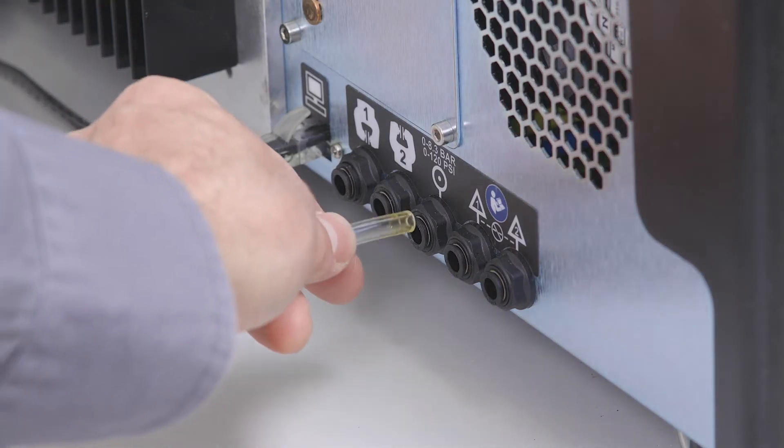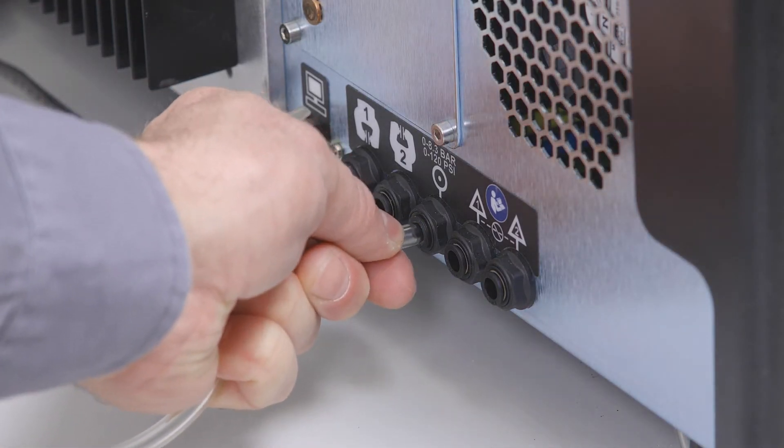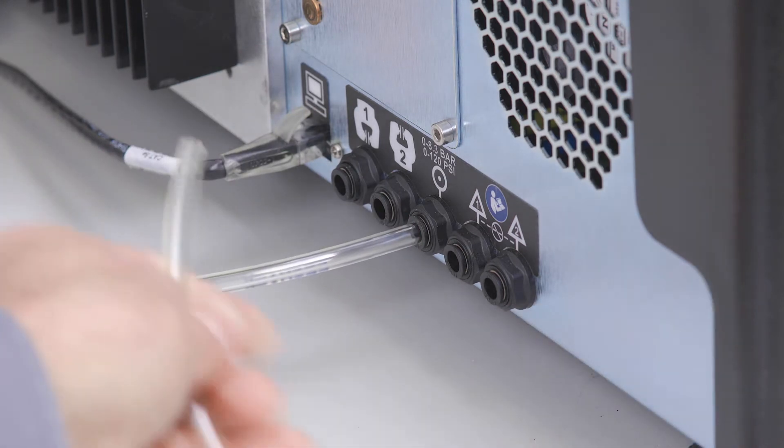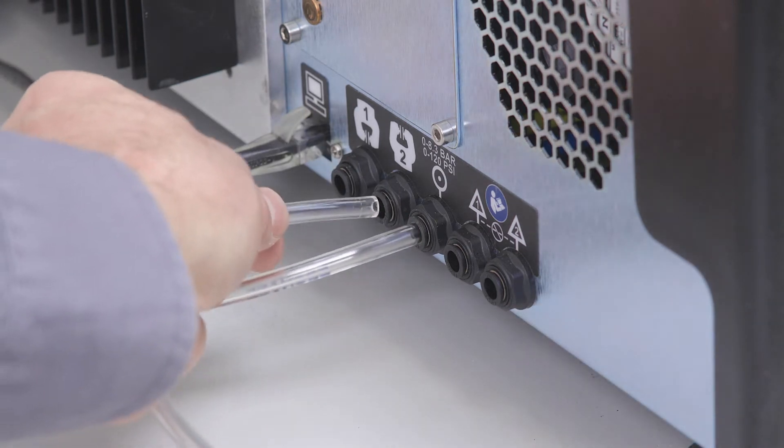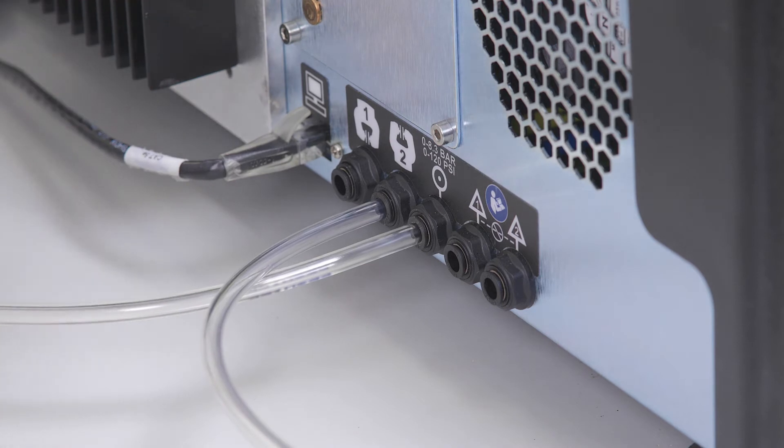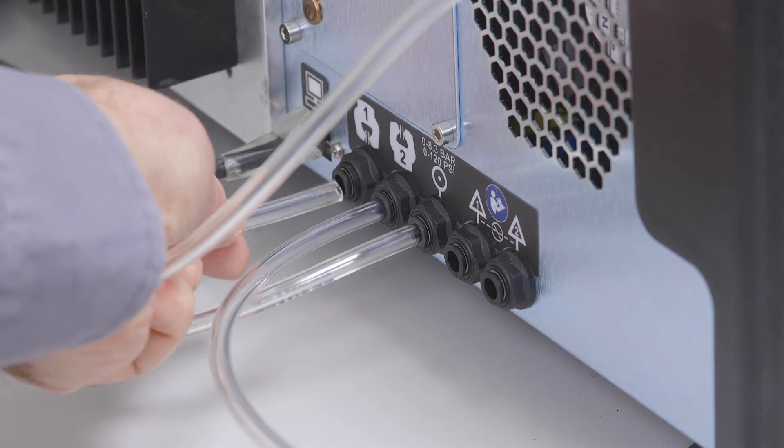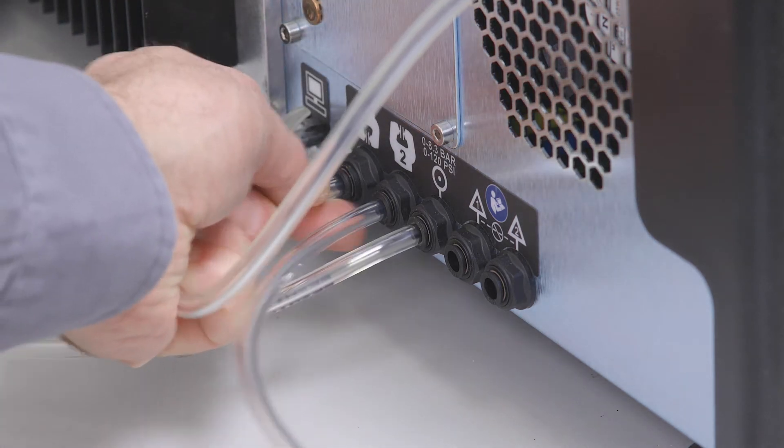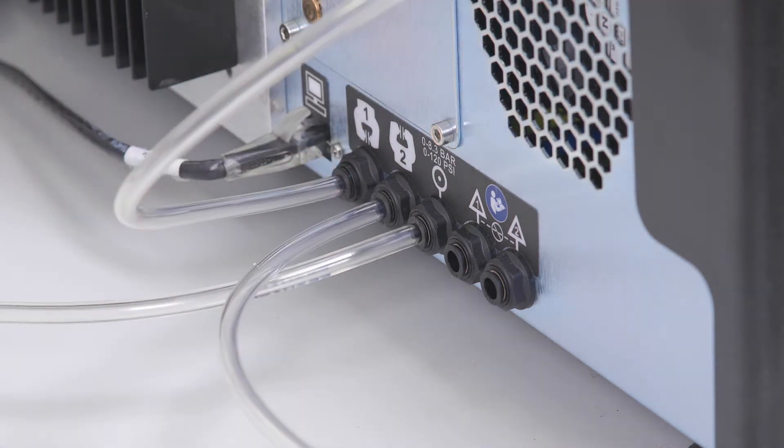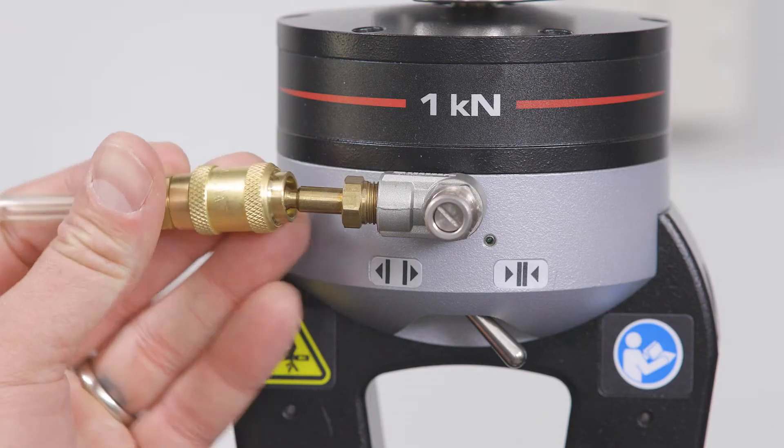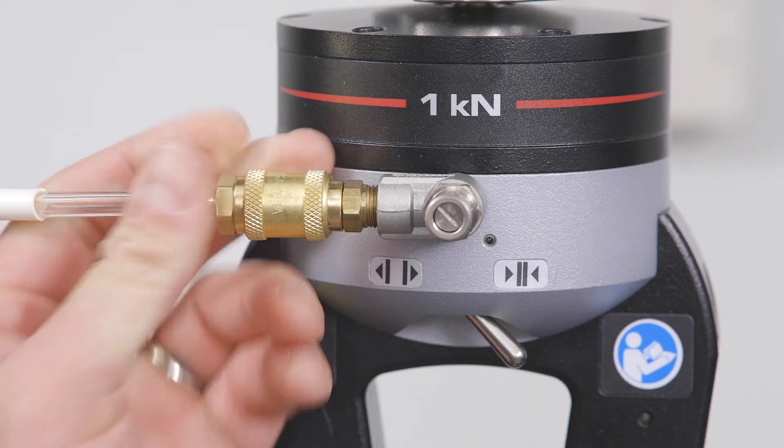The Smart Close Air Kit features a software-controlled dual-stage regulator integrated into the testing system, allowing for easy management of pneumatic lines. Once the inlet air is hooked up, any changes to the pressure can be made within the software, and there is no need to adjust the regulator between tests.